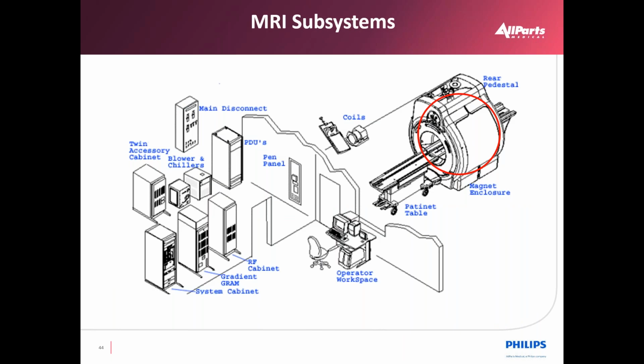There is also a gradient coil installed in the magnet bore. The gradient coil is a large cylinder made of fiberglass and epoxy. There are copper strips embedded in the coil that make up the X, Y, and Z gradient axes. They produce gradient magnetic fields that adjust the strength of the magnet in certain areas to help define the image plane and the slice thickness of the image.